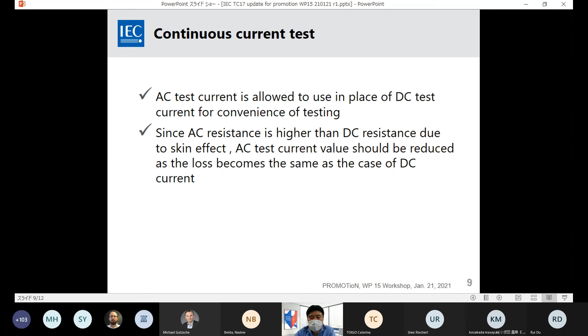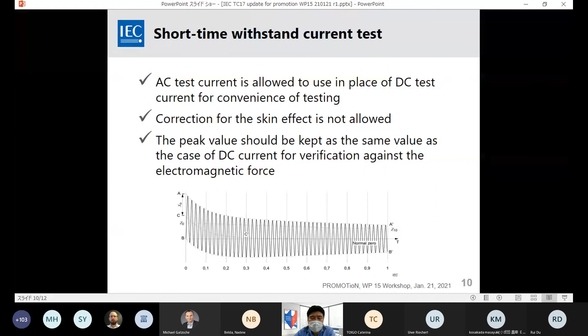Finally, concerning short-time withstand current test, in this test, AC test current is also allowed to be used instead of DC current for convenience of the test. But the correction of the skin effect is not allowed in this case. And the peak values should be kept the same as the case of the DC current for verification against the electromagnetic force.